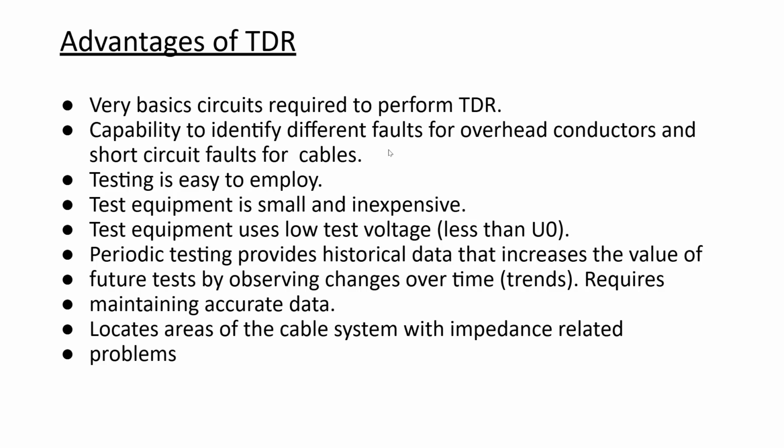So it has the capability to identify different faults for overhead conductors and short circuited faults for cables. Testing is easy to employ. Test equipment is very small and inexpensive. Test equipment uses low voltage, less than U0. U0 means line voltage. So very low voltage is required for this.